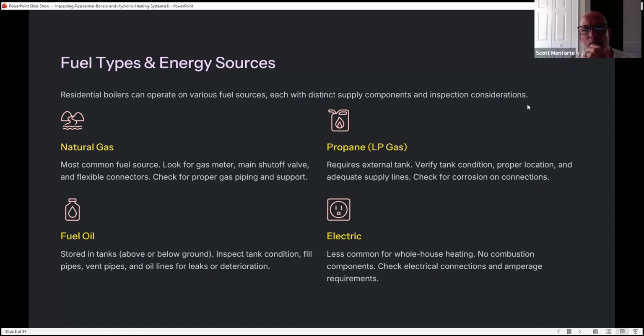It was Paraco Gas. Paraco Gas, that's right. So there's a Paraco Gas webinar. You can watch that for proper propane tank information and such. Fuel oil is stored in tanks above and below ground. Inspect tank condition, fill pipes, vent pipes, and oil lines for leaks and deterioration. And we have electric, which is less common for whole house heating. There are no combustion components, and you want to check for electrical connections and amperage requirements.